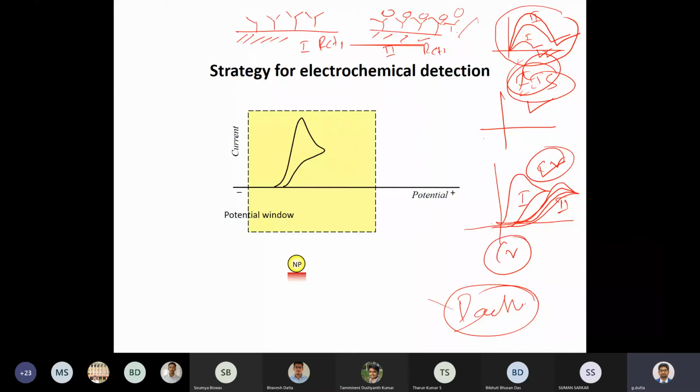Sometimes outside material can decrease their efficiency. That's why your impedance can be increased. You may think the concentration of target is increasing, but it's not; it's because the outside contaminant is increasing the EIS. That's why your cleanliness, your storing technique, and packaging should be done very carefully. Clear? Yes, sir? This is very important.